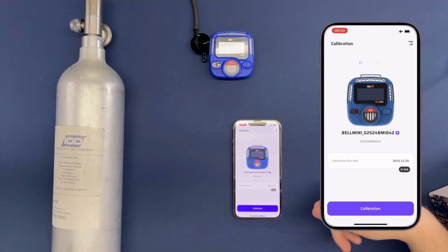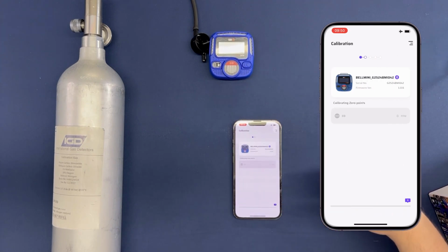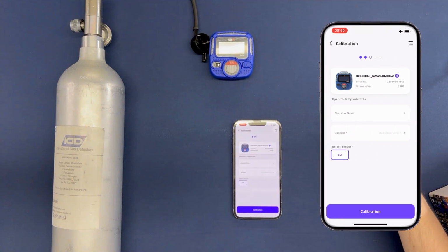So if we press calibration, the first thing it will do is zero the sensor on fresh air. So make sure you are outside of the environment and are in fresh air. So if we press calibrate, it will just do a 0 right now. As you can see on the BELLMINI, it does say pass, and it says pass on here.